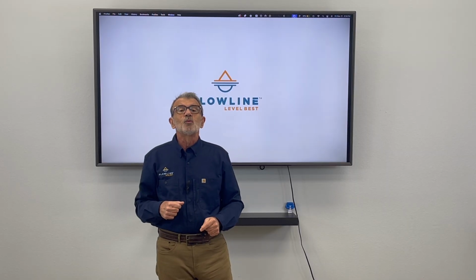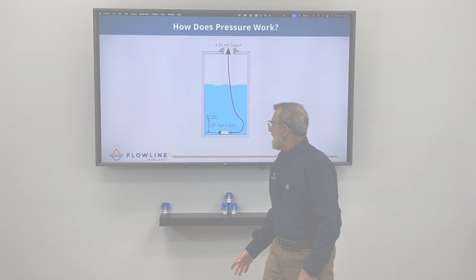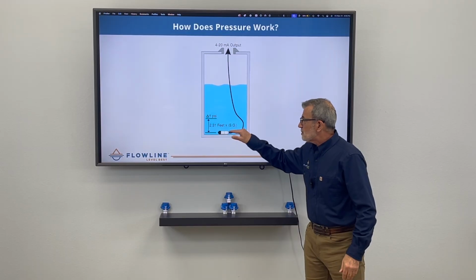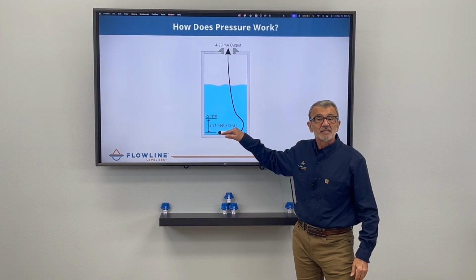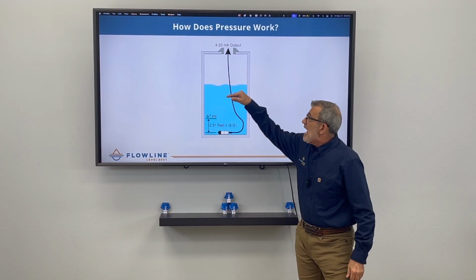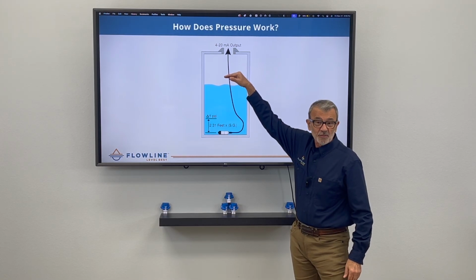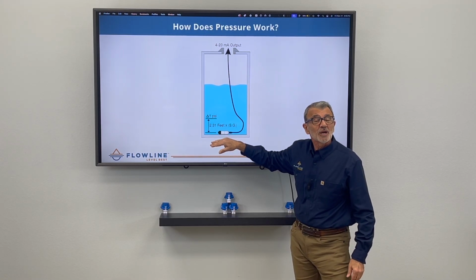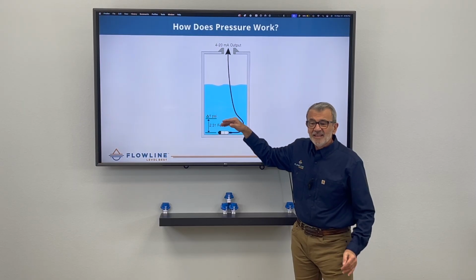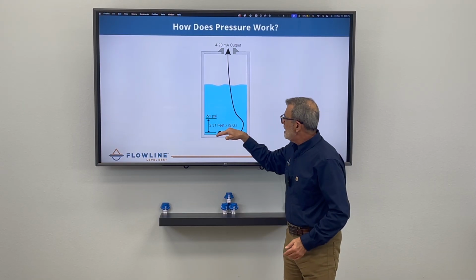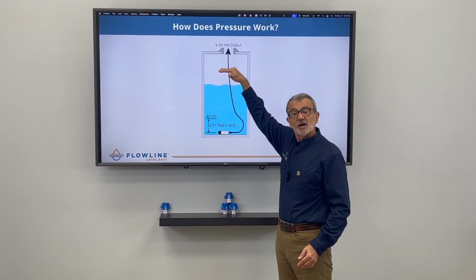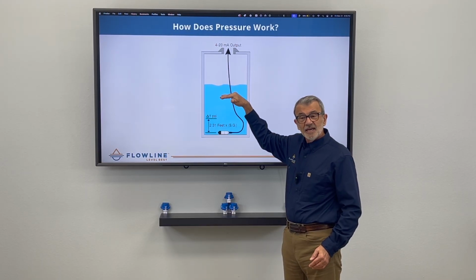Let's talk about how it works first. If I was able to measure pressure down at the bottom of a tank that's got liquid in it, the higher the level, the more pressure is applied to the pressure element. The lower, the less. So it's a very simple concept. Measure pressure here, and it will give you where the level is in the tank.